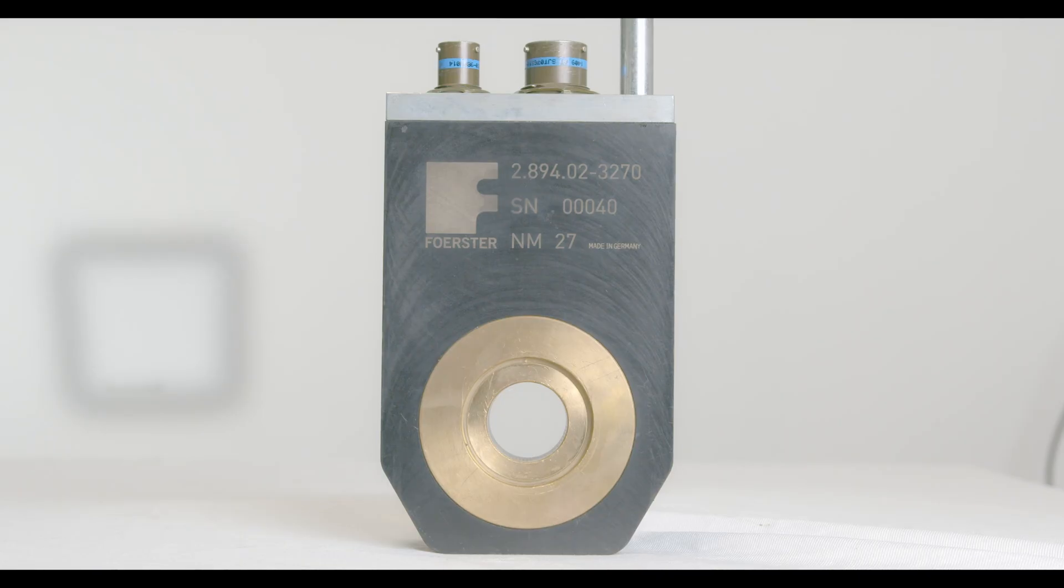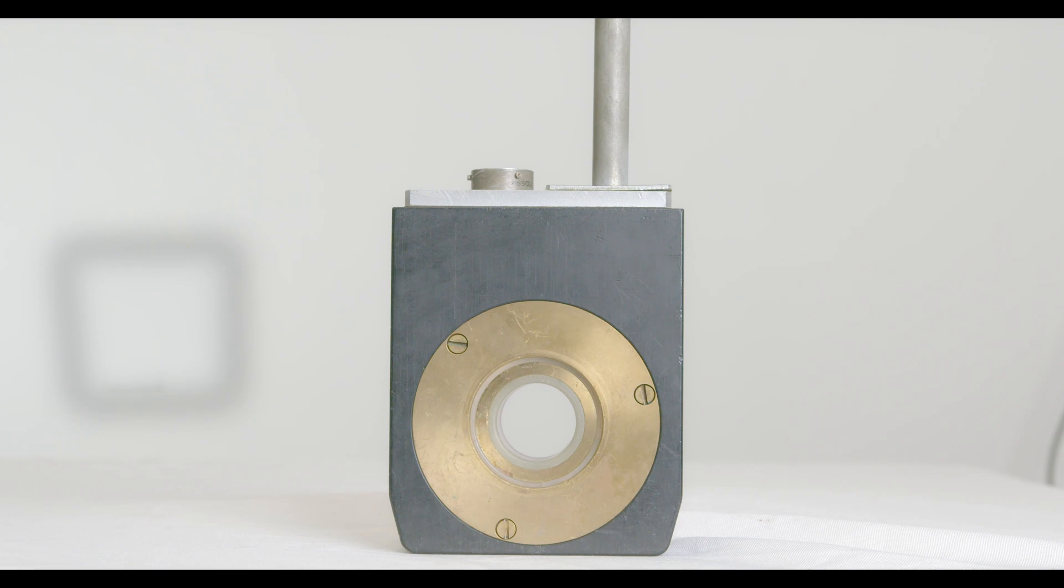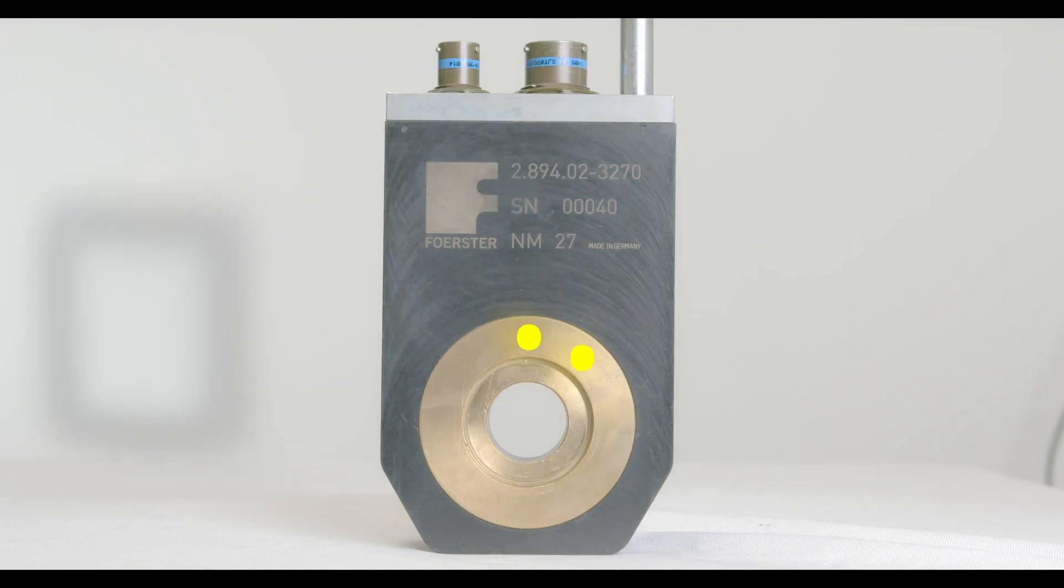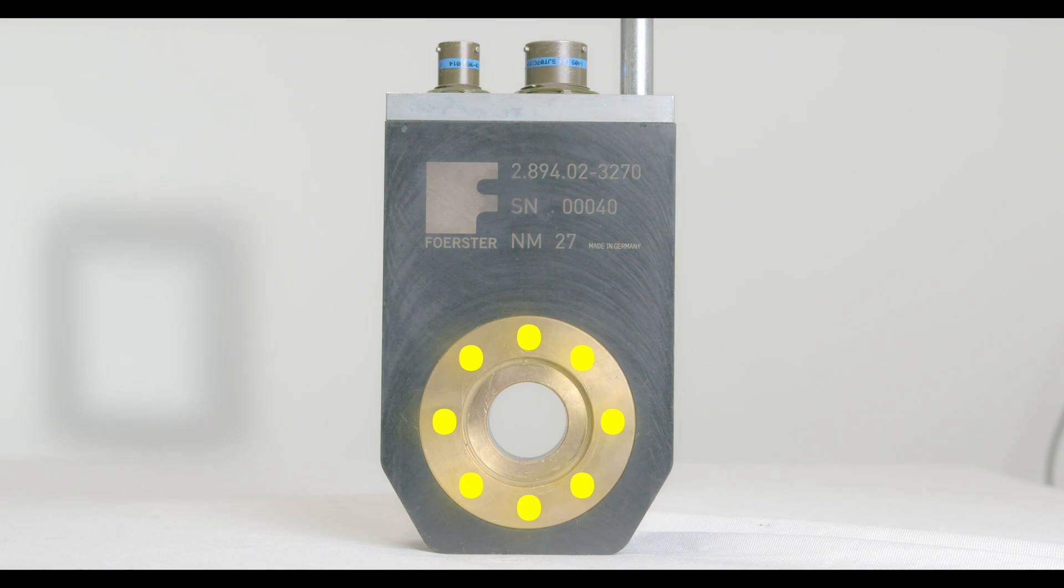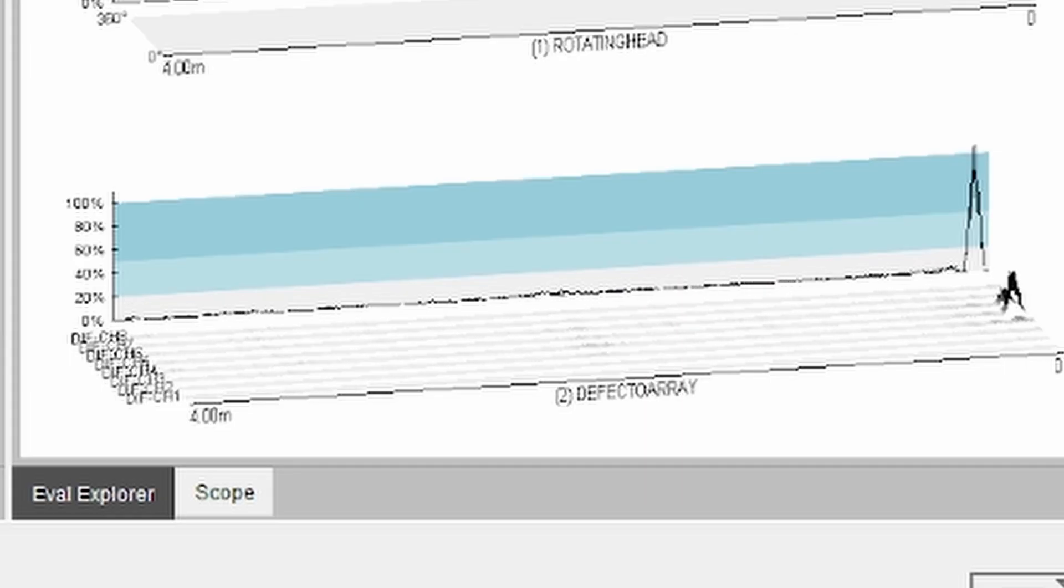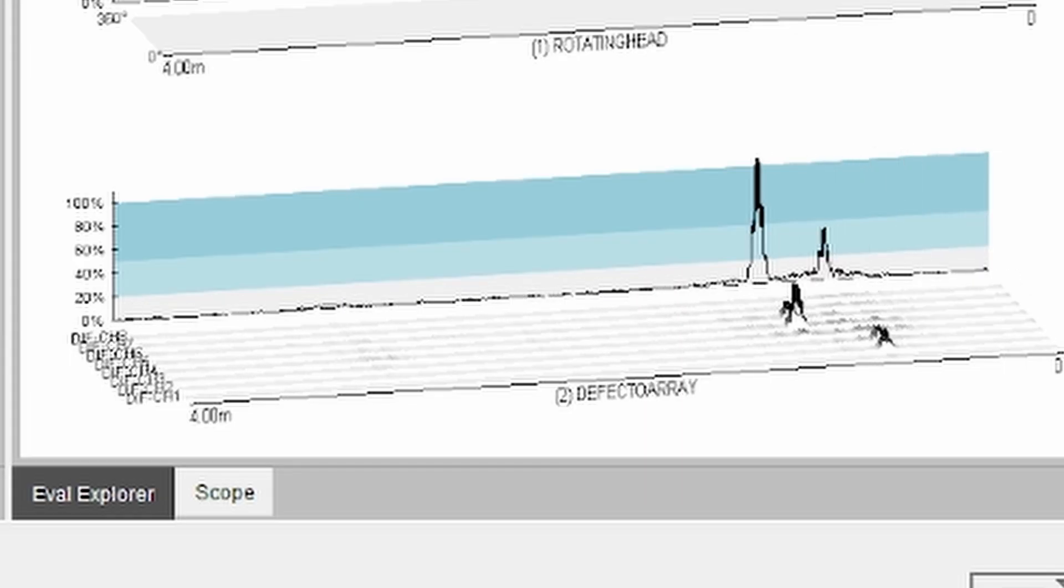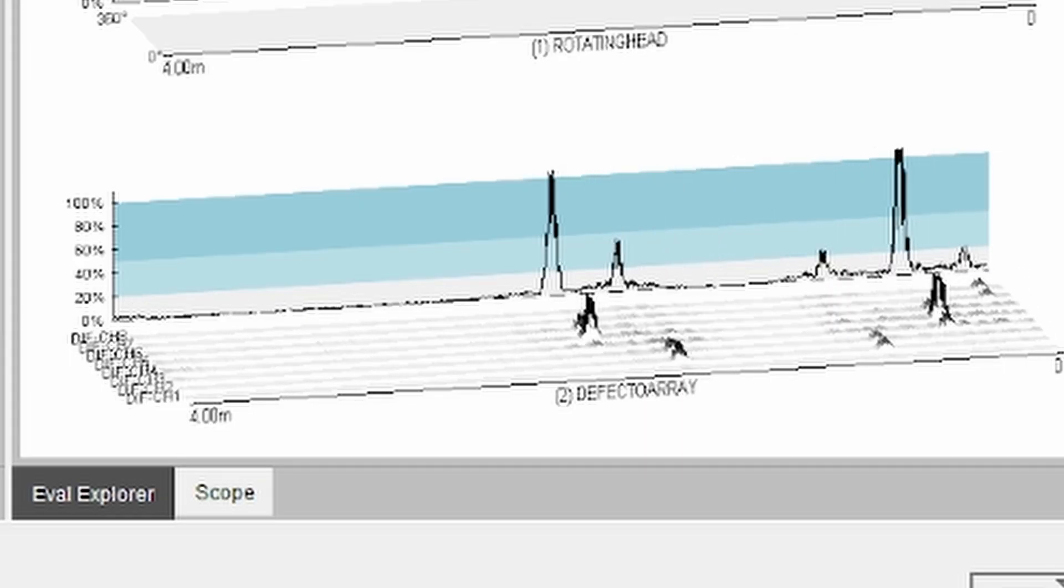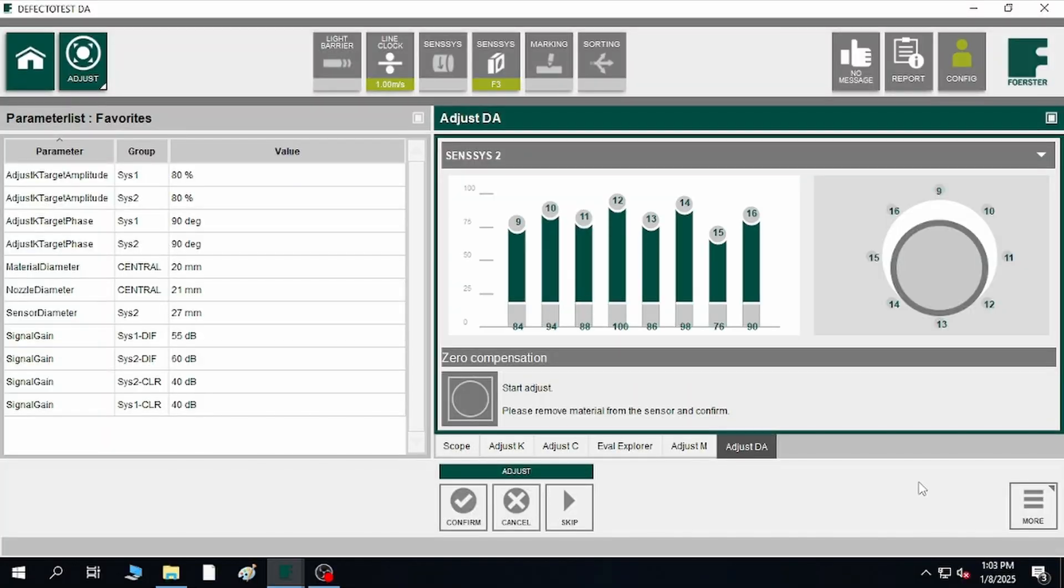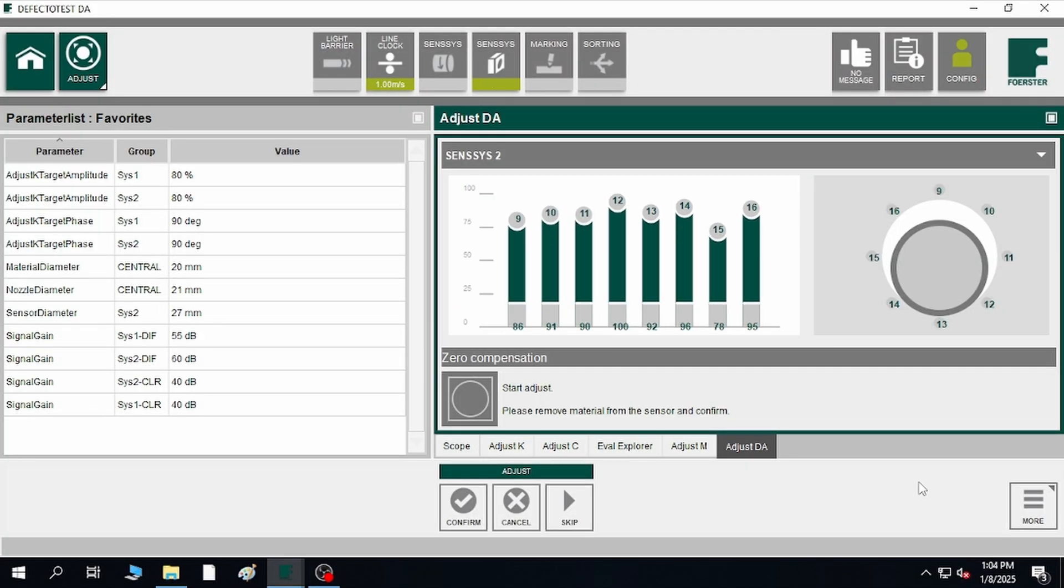The new array coil is like our standard coils. However, now there are eight segmented channels built into one coil. Paired with the DA, it becomes much easier to pinpoint the exact location of defects. It also allows for controlling the signals if the material moves off its center line.